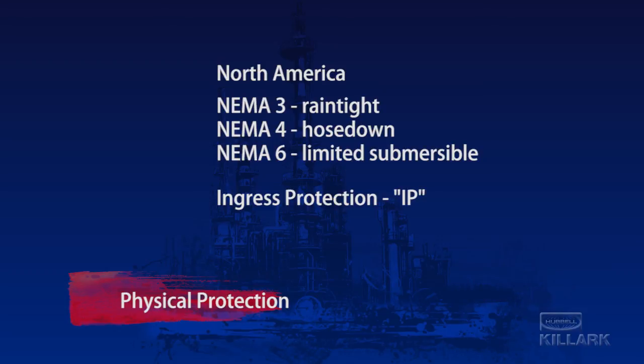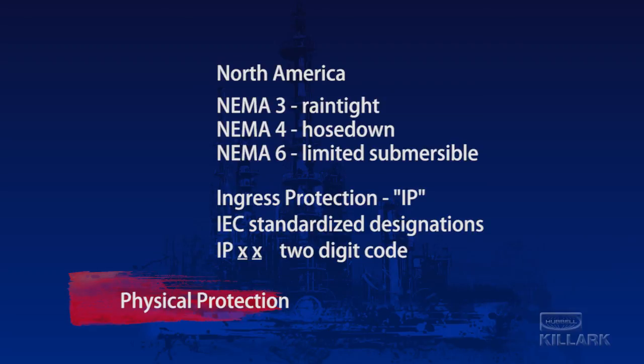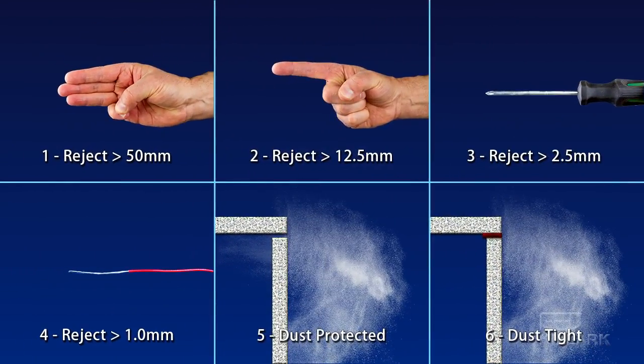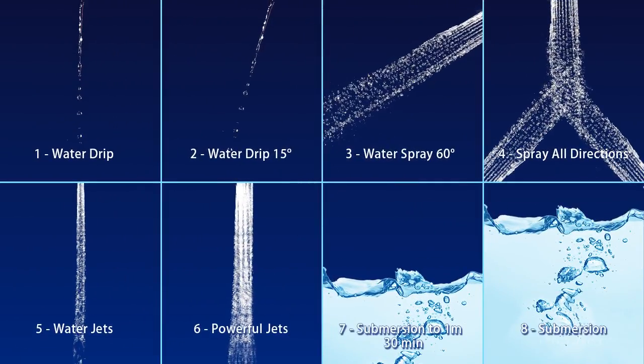Ingress Protection, or IP, is the rating system standardized by the IEC. It uses a 2-digit code to assure that the proper physical safeguards are in place for the EX protection type selected and its environment. The first digit following the IP designation denotes the extent to which the internal components are shielded from inadvertent or intentional access or foreign objects. The numbers range from a low of 0 with no physical safeguards provided up to level 6, which is fully dust-tight and prevents access even with a probe as small as a fine wire. The second digit signifies the degree of protection afforded against the entry of water. In this case, there are 8 levels of entry safeguards, ranging all the way through protection from continuous submersion in depths greater than 1 meter.